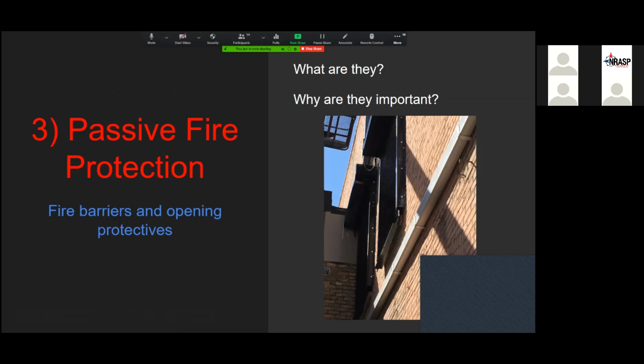Let's move on to number 3, passive fire protection. So we're going to talk about fire barriers and opening protectives. A passive fire protection system means it's doing its job strictly by just being there, like a firewall. A closed fire door is also passive fire protection. Now, if you have a fire door that's open and designed to close as a result of heat or smoke, this technically falls under the active fire protection systems. We're going to talk about them now just because it's easier to talk about it all at once.